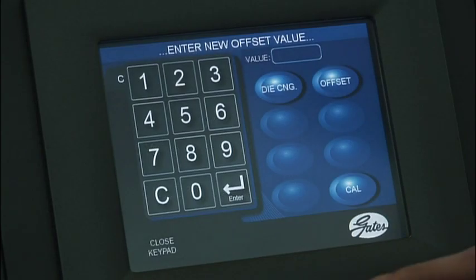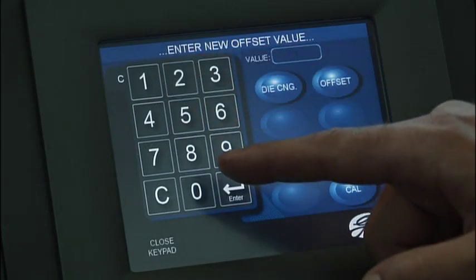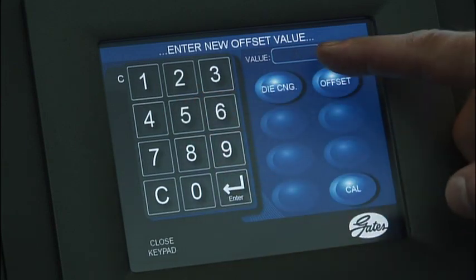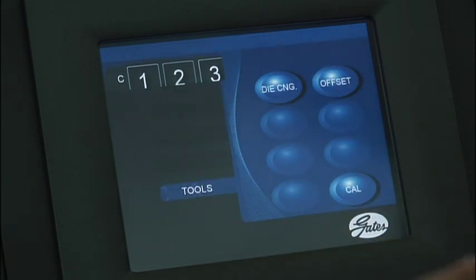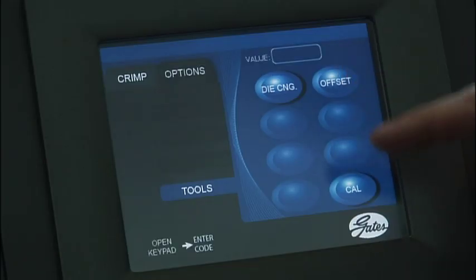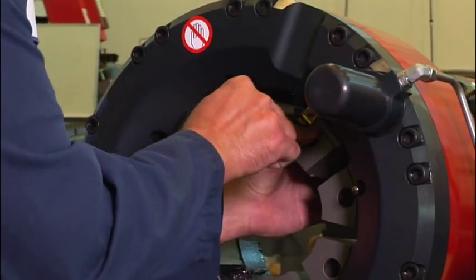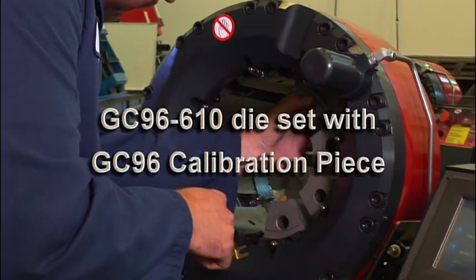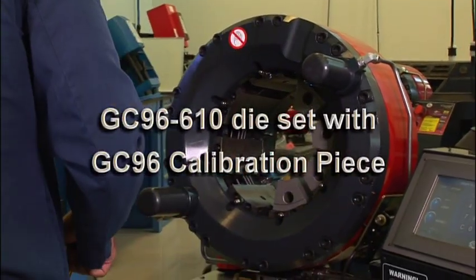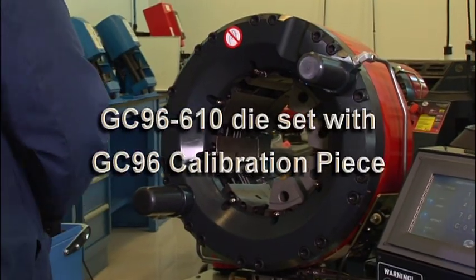Please note, if the Enter key is not pressed, the new offset value will not be loaded. Repeat the calibration steps until the published crimp diameter is achieved. The crimper is now calibrated. The second calibration method utilizes the GC96-610 die set and the GC96 calibration piece.